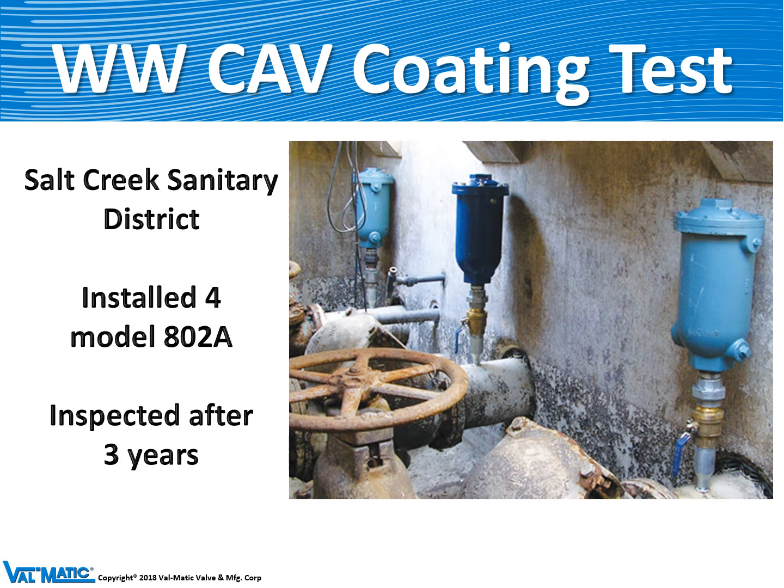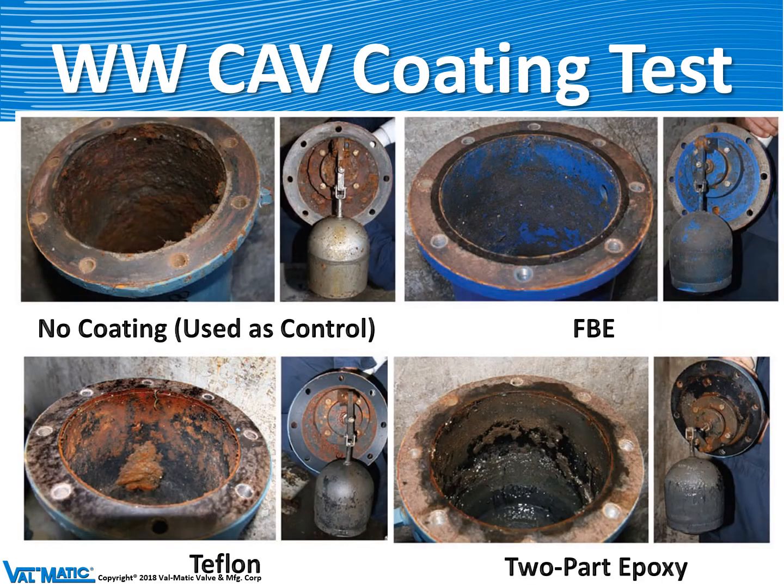We did an interesting test about 10 years ago at Salt Creek Sanitary District. We installed four of our wastewater air valves, Model 802A, with different interior coatings: bare interior, two-part epoxy coating, Teflon coating, and fusion bonded epoxy coating, to see which coating prevents clogging. After three years, the valve with no coating had severe debris buildup, Teflon was a little better, epoxy was pretty good, but the best performing valve was fusion bonded epoxy — the blue coating — and that is what we recommend for wastewater service to prevent fouling of the valve.